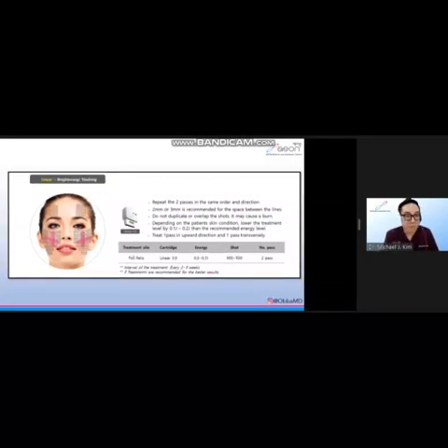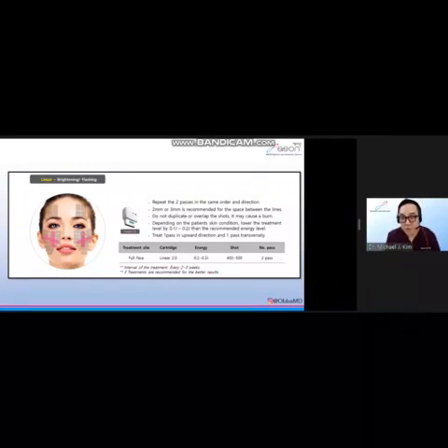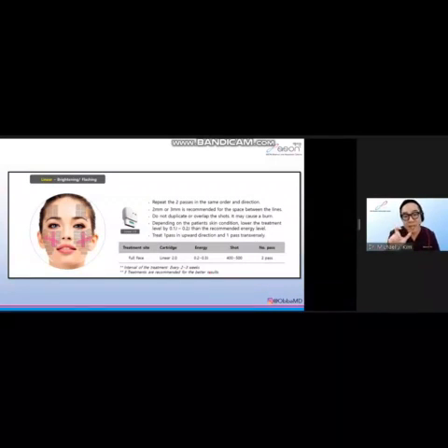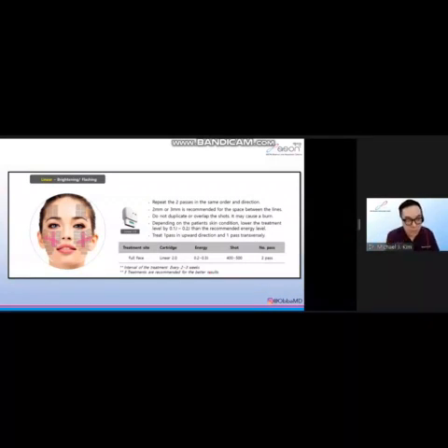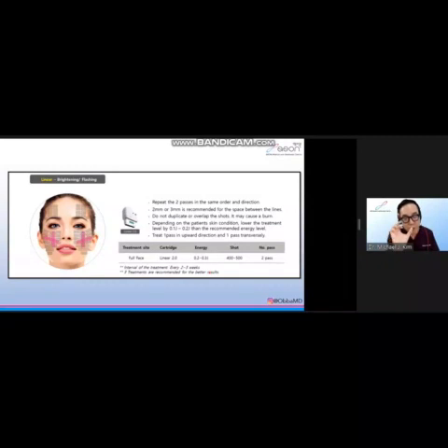For the 2 mm linear, I use it for all areas usually treated with the HIFU, so the neck, cheeks, temples, but I don't use it on the forehead because you cannot adjust the length of the line, which on the forehead contour can be risky. So with the dot cartridges, as you know, you can adjust the length of the line you're using, but for the linear, you cannot. It's 25 mm and set.